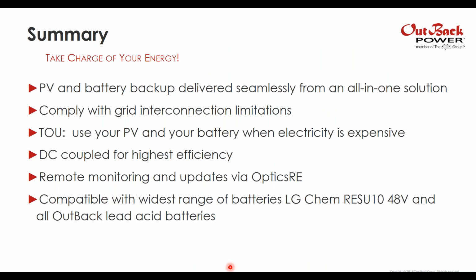So in summary, SkyBox allows you to take charge of your energy. It provides PV and battery backup delivered seamlessly in one simple, easy to install, one box solution. Complies with all grid connection and interconnection limitations and rules, such as California Rule 21, HECO 14H, et cetera. It gives you time of use energy optimization so that you can use your battery and your PV when electricity is expensive. It is DC coupled for highest efficiency. Remote monitoring is available via Optics RE, the industry leading solar plus storage monitoring site, and SkyBox is compatible with the widest range of battery chemistries, from your LG Chem 48 volt residential to all OutBack Power lead acid batteries and any lithium ion battery pack that's 48 volts and behaves like a lead acid battery.